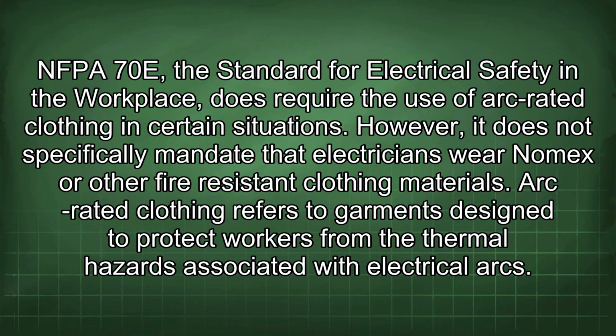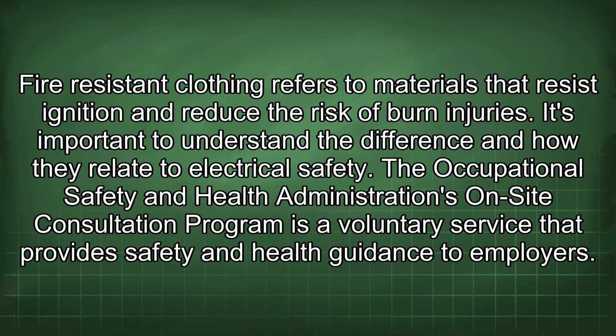NFPA 70E, a standard for electrical safety in the workplace, does require the use of arc-rated clothing in certain situations. However, it does not specifically mandate that electricians wear Nomex or other fire-resistant clothing materials. Arc-rated clothing refers to garments designed to protect workers from the thermal hazards associated with electrical arcs. Fire-resistant clothing refers to materials that resist ignition and reduce the risk of burn injuries. It's important to understand the difference and how they relate to electrical safety.